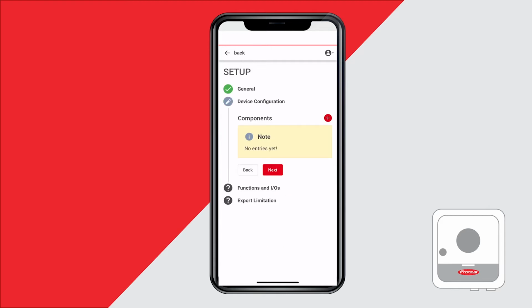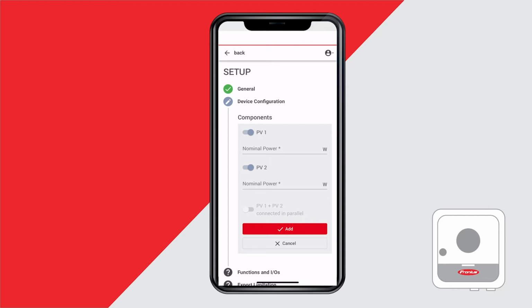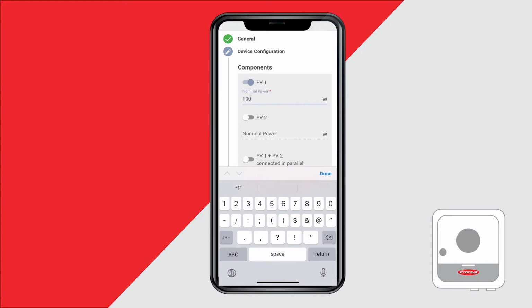The next part is to add different components, so you'll need to add one. If I click on the plus button there, you have PV generator, power meter, or battery. So let me select PV generator. You can see your first tracker PV1 and your second tracker PV2. If they are both parallel, connected together, you can select PV1 plus PV2 if you want. So I'll just turn PV2 off, put 1000 watts for PV1, and click on add.